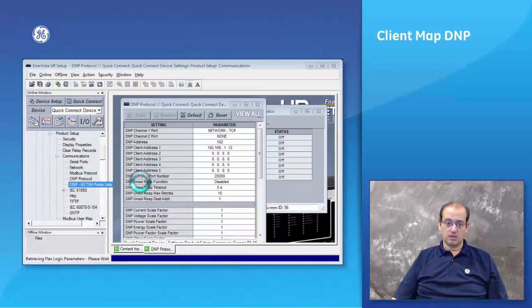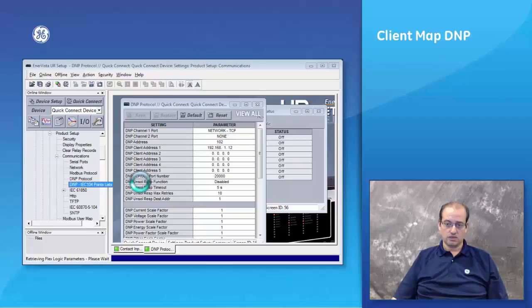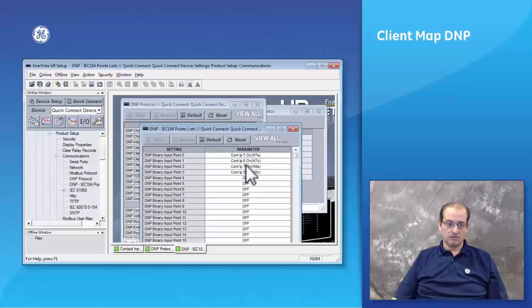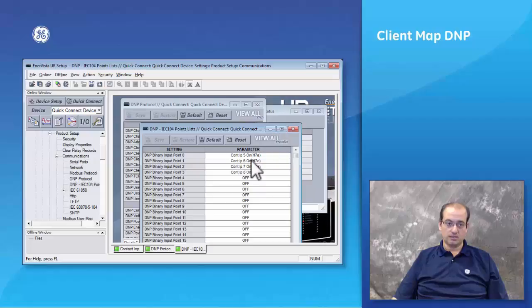In the point list of the DNP we only have mapped four digital inputs. There is no analog inputs, which is those four digital inputs that we did. You can see contact input number five, contact input number six, contact input number seven, contact input number eight.